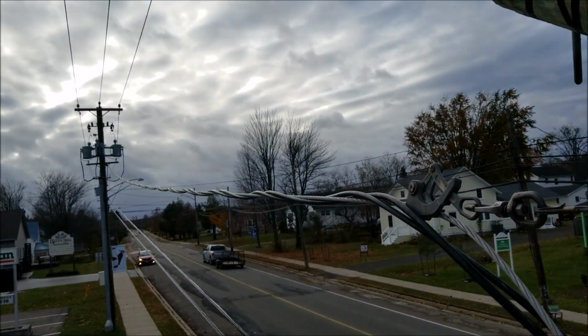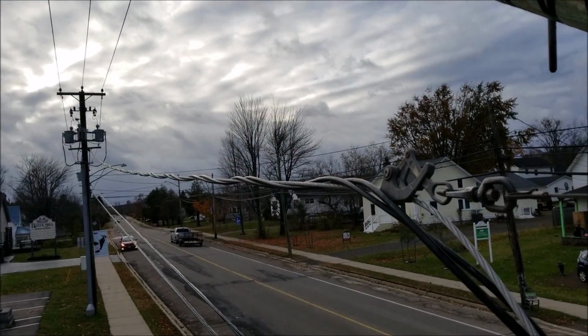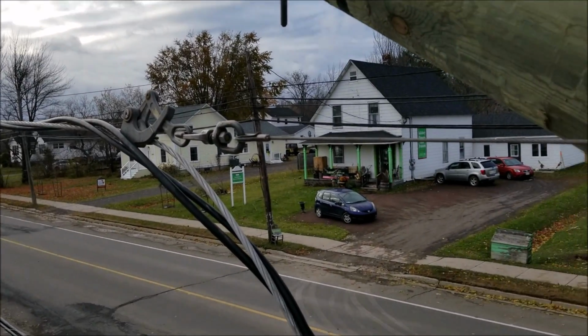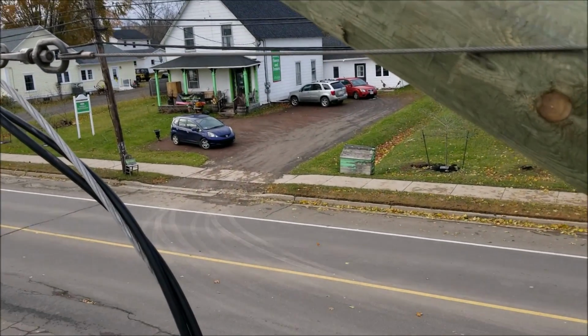So first thing we did was actually jumper out the neutral wire, thus eliminating any voltage difference between the two sides of the broken wire.